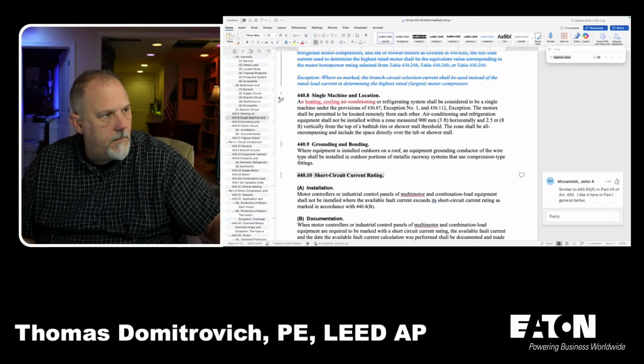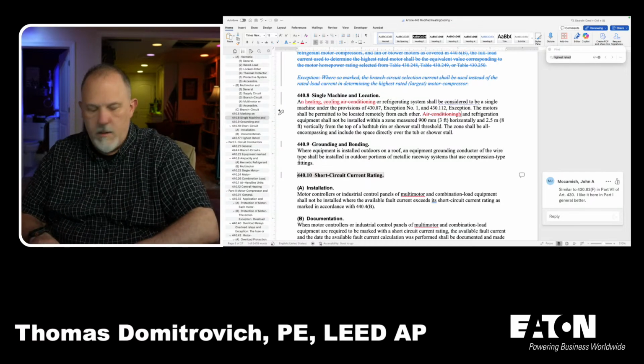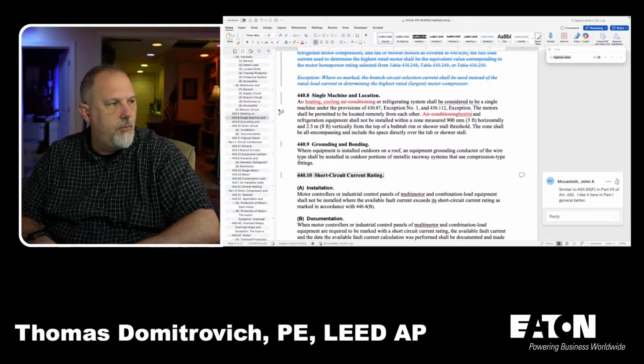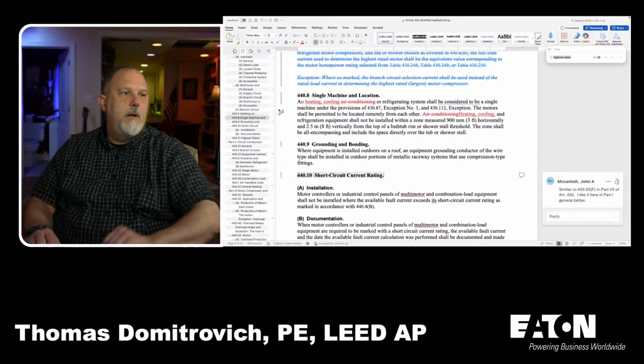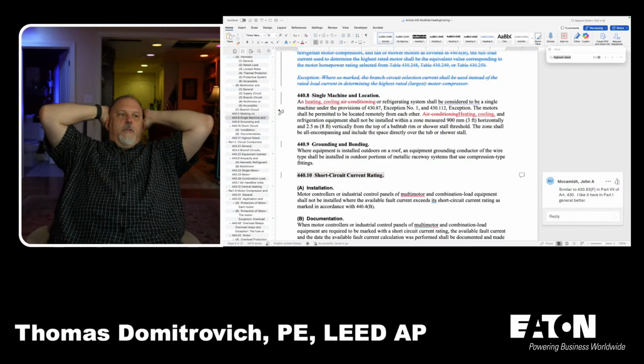Heating, cooling, and refrigeration equipment shall not be installed within a zone measured 3 foot horizontally and 8 foot vertically from the top of a bathtub rim or shower stall. The zone shall be all-encompassing and include the space directly over the tub or shower stall.